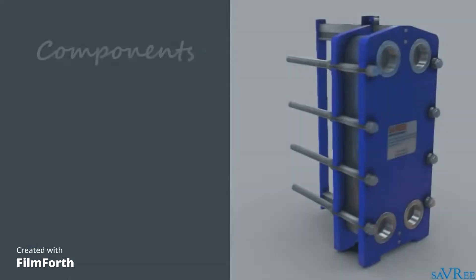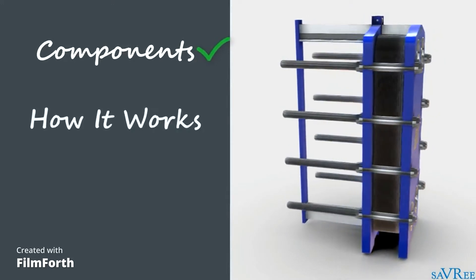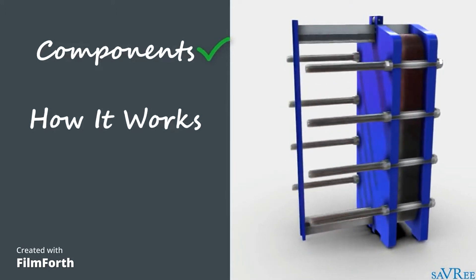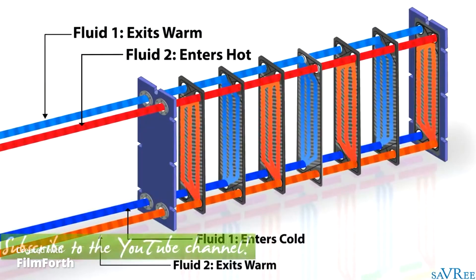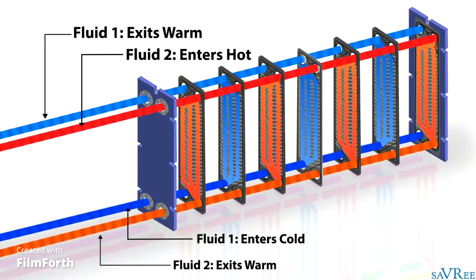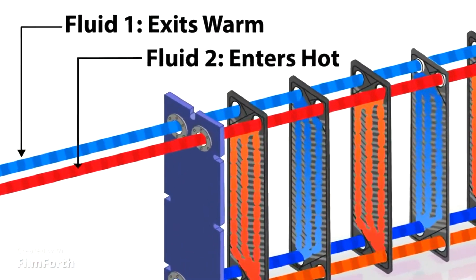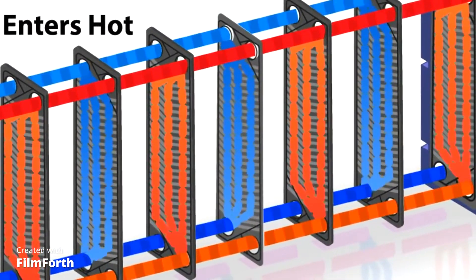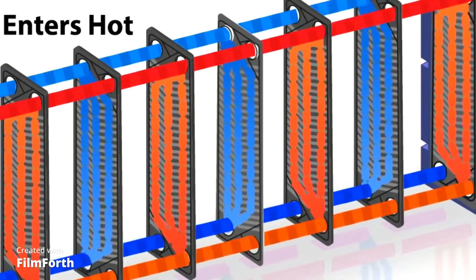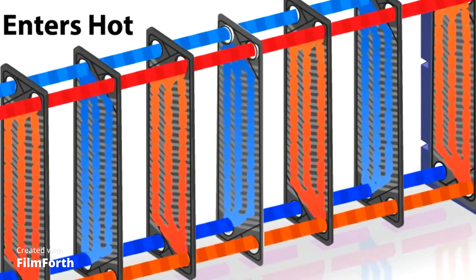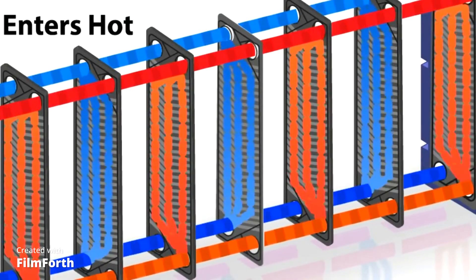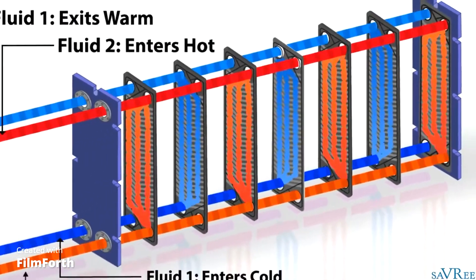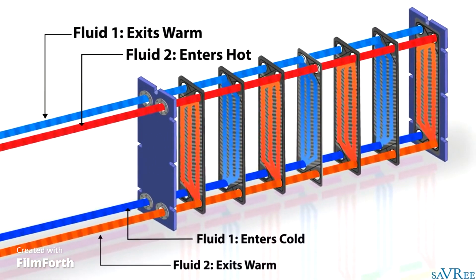Now we know the plate heat exchanger's main components, let's look at how it works and some of its design features. For demonstration purposes, we will assume we have two flowing mediums — one cold and one hot. The hot medium enters through the hot medium inlet. Gaskets direct the hot medium as it flows through the heat exchanger. Each plate has an alternating gasket pattern, so the hot medium flows into the space between a pair of plates but does not flow into the next pair because the gaskets prevent this.